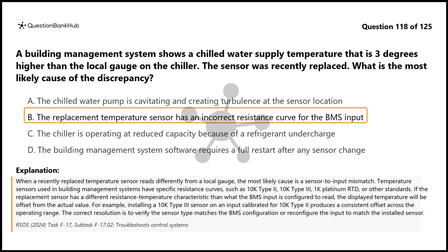If the replacement sensor has a different resistance temperature characteristic than what the BMS input is configured to read, the displayed temperature will be offset from the actual value. For example, installing a 10K Type III sensor on an input calibrated for 10K Type II produces a consistent offset across the operating range. The correct resolution is to verify the sensor type matches the BMS configuration or reconfigure the input to match the installed sensor.